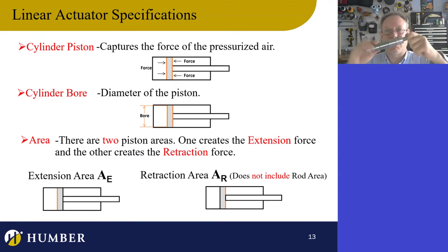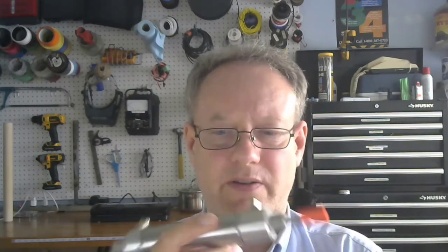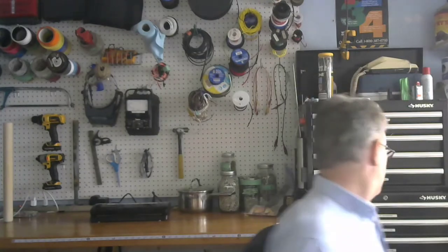Let's get into actuator specifications — the parts, names, and mechanisms. There's a piston inside; air presses against one side or the other to create force, making the cylinder extend and retract. There are seals around the piston — I'll put links to videos about seals on Blackboard. The key parts are: the rod, the piston inside, the cylinder body, and the ports. This is a double-acting cylinder; I also have a single-acting cylinder with a spring return.